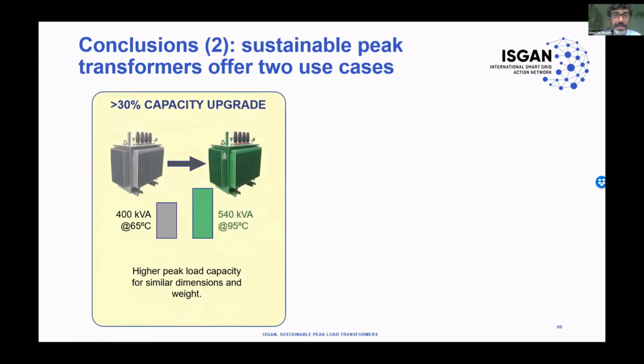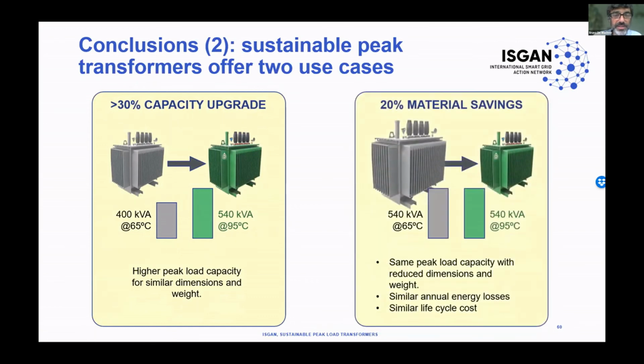Next slide, please. There are two main advantages of this concept. The first one is a capacity upgrade of around 30% that is possible without increasing the dimensions or the weight of the transformer. So transformers can just be exchanged and increase their peak load without any further changes to the site. The second big advantage, which is an increasing concern in many regulatory instances around the world, is material savings. Here we see that for the same peak load capacity, we have a smaller transformer and consequently also much less material use, and this for similar annual energy losses and a similar life cycle cost.